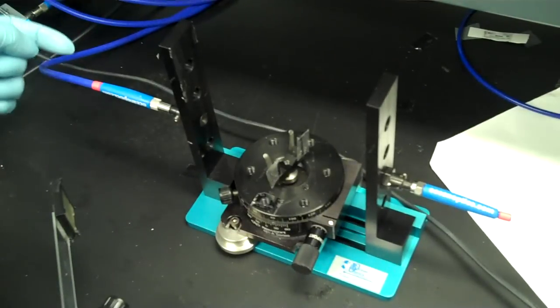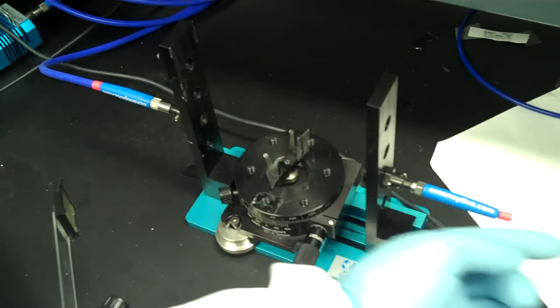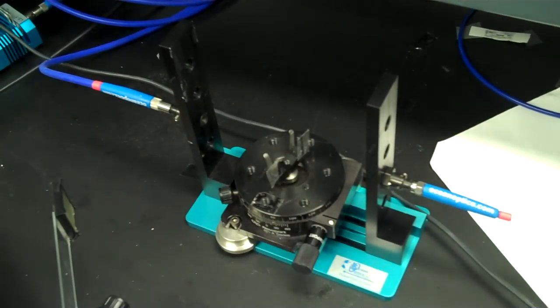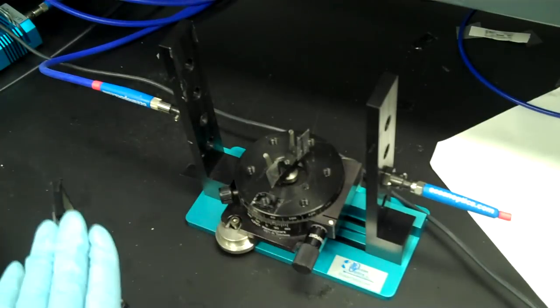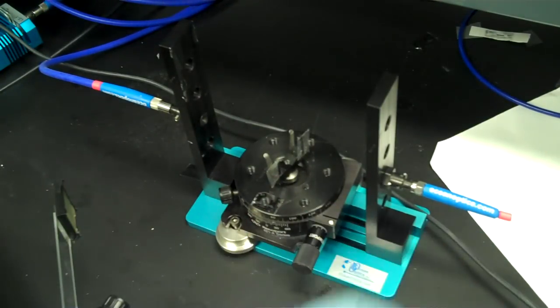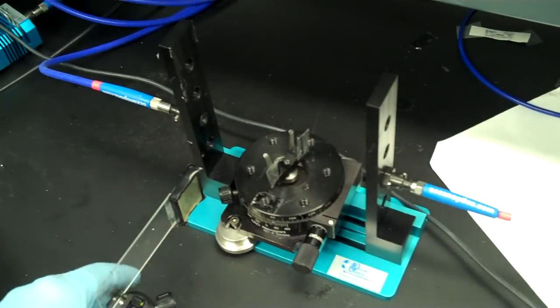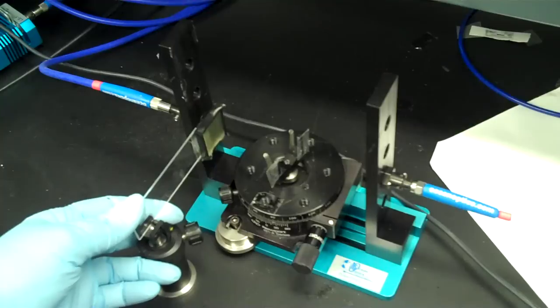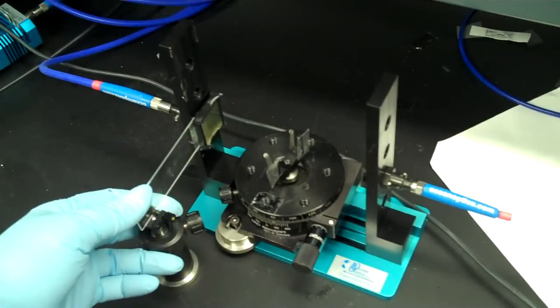A fiber optic cable coming through here. Our sample goes in here, and then another fiber optic cable going out. And there's a white light being passed through this cable. It diffracts from our filter, and then it goes into the other cable. And at the end of that is a spectrometer that measures the percent transmittance at each wavelength. So I'm going to place my filter in the path of the beam here.